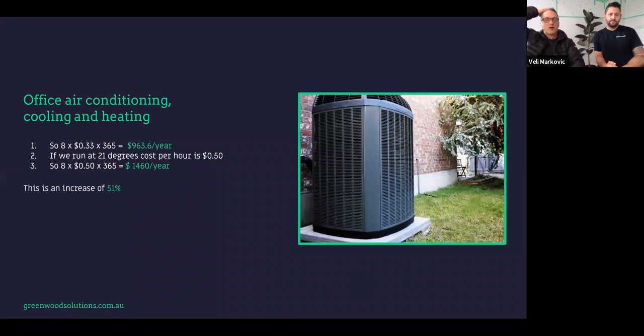So that one air conditioner is costing $963 a year. Now, if we suddenly want to run it at 21 degrees, the cost per hour goes up to 50 cents, and our cost per year is $1,460. That's an increase of 51%, which is massive, just by changing the temperature a few degrees. So just be aware it's a non-linear relationship between lowering the temperature in your office during summer and raising the temperature during winter.